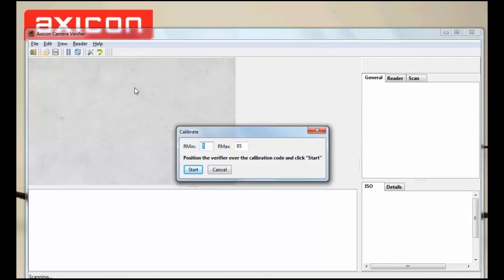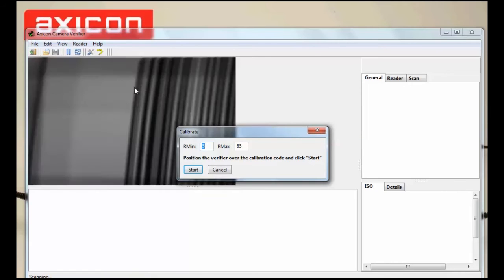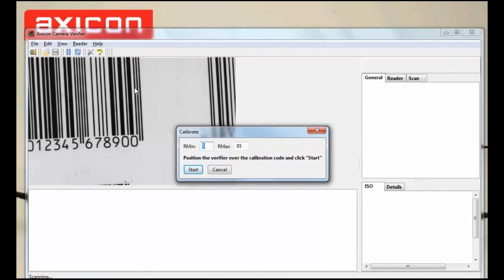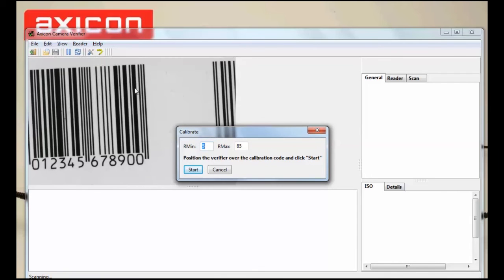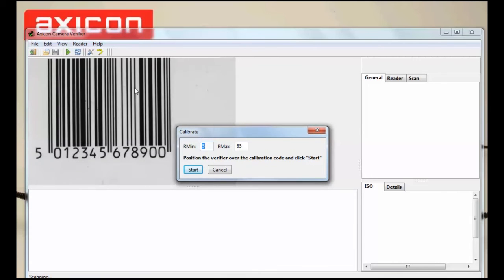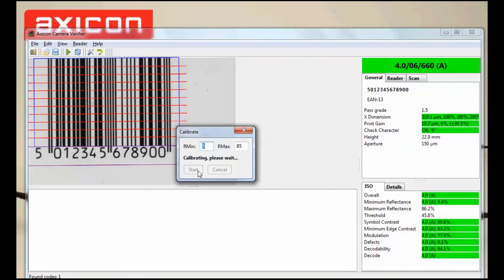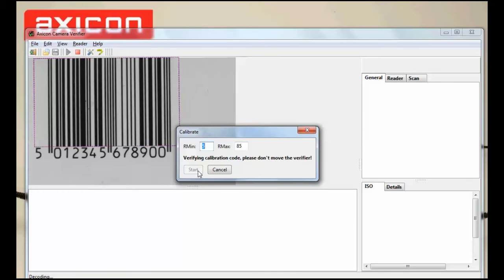Position the EAN13 barcode on the calibration sheet so it's in view. Make sure the minimum and maximum reflectance match what is on the calibration sheet and then press Start. Calibration should only take a couple of seconds and then we are ready to go.